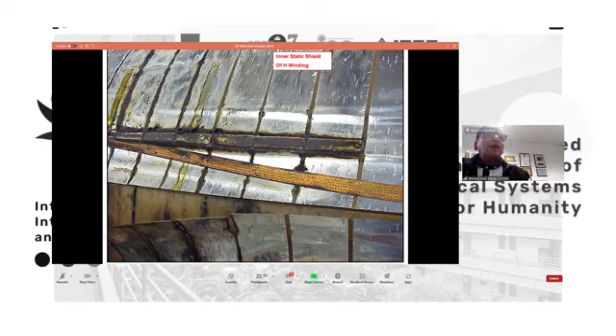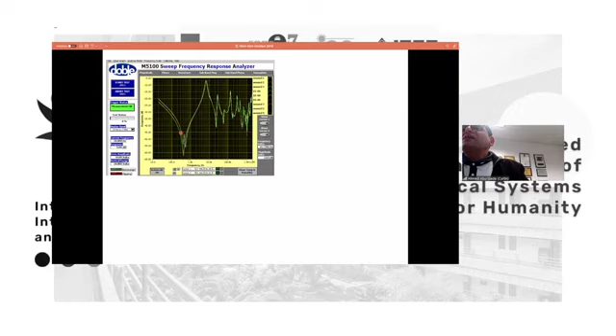If we look at another example, this transformer, you know now the three phases here are similar to each other. The one to the left here is the middle phase, which is normal. So this transformer is healthy, nothing wrong with it. But if you look at this one, we have significant deviation among the three phases of the transformer, which reveals a significant problem in at least two phases. So when we took the transformer out of service, can you see that a very strong electromechanical fault happened inside the transformer?